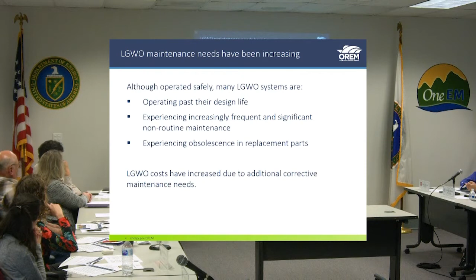Increasing frequent and significant non-routine maintenance—pipes leak, they break. We have pumps that fail, electrical switches that fail, things like that becoming more and more frequent. And it's getting hard to find replacement parts for a lot of it. One example I'll talk about in a minute is the motor control centers, some of the switch gears for the electric switching of the electric feeds to different parts of the plant. It's getting hard to get replacement parts, so they need to be upgraded.